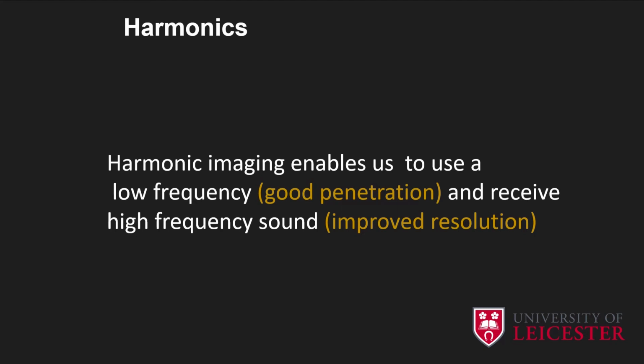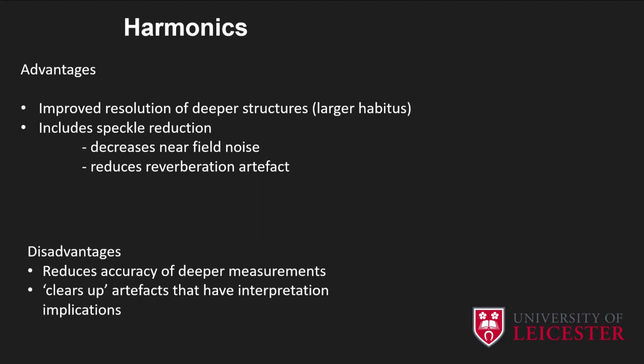Therefore, we can use a low frequency sound, get good penetration, and at the same time see only the high frequency echoes, which improves our resolution. This means that scanning patients with larger body habitus is no longer a disadvantage. So harmonic imaging offers huge benefits and really improves the quality of the images we can produce. It's associated with fewer artifacts than conventional ultrasound. Disadvantages include accuracy of measurements and also clearing up artifacts that can represent beneficial information, and we'll look at that when we go to artifacts in the next few slides.